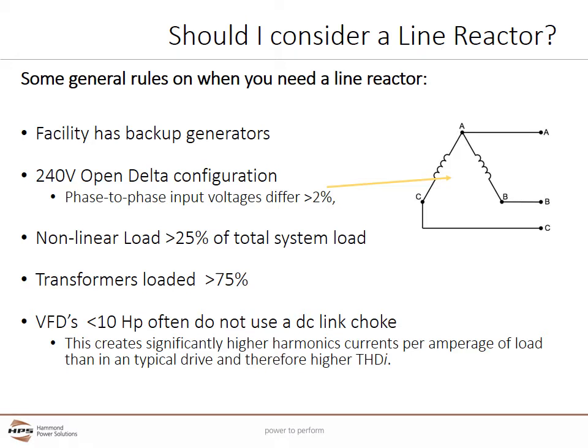Here are general rules on when you need a line reactor. If the facility has backup generators, they must be sized to supply both motor load and additional current harmonics. By reducing current harmonics, line reactors may allow sizing of a smaller, less expensive generator. 240-volt open delta circuits are often associated with phase-to-phase voltage differences which can cause current imbalances in the VFD's rectifier circuits, potentially causing the VFD's lifetime to lessen or fail outright. If installing a VFD in a 240-volt open delta configuration, a line reactor in front of it is recommended.